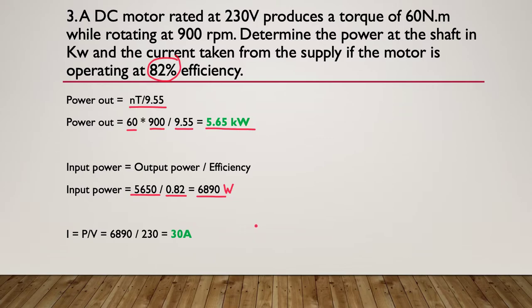Of course, we want to find out what that current is. So it's down to Ohm's law. I equals the power divided by the voltage. So here's our power in divided by our voltage, which was given to us in the question, and it rounds out to a nice 30 amps. So 5.65 kilowatt output power and 30 amps input.